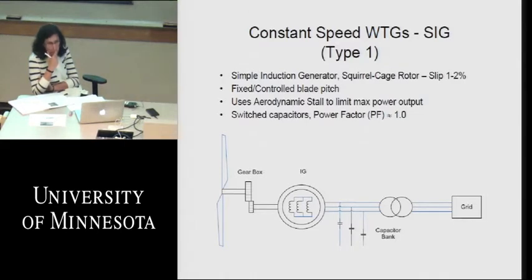Because it does use a simple induction generator, which will have a power factor of 0.87 or 0.90 or such, inductively, it means it's drawing VARs from the grid into the machine, and in doing so, it will tend to drop the voltage on the grid as it's pulling those VARs off the grid. So what we do is we have a set of capacitors in the wind turbine that will offset the inductive nature of the generator itself with capacitive current. And of course, the vector nature of inductance and capacitance is that they are diametrically opposed to each other, and so they will tend to cancel each other.